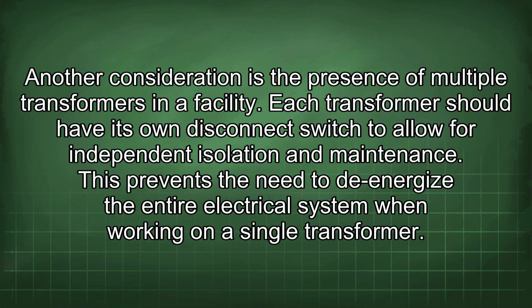Another consideration is the presence of multiple transformers in a facility. Each transformer should have its own disconnect switch to allow for independent isolation and maintenance. This prevents the need to de-energize the entire electrical system when working on a single transformer.